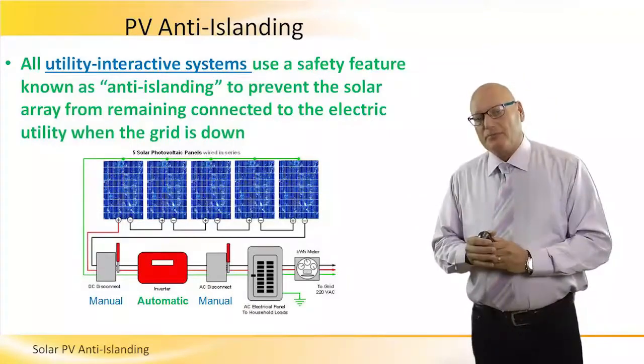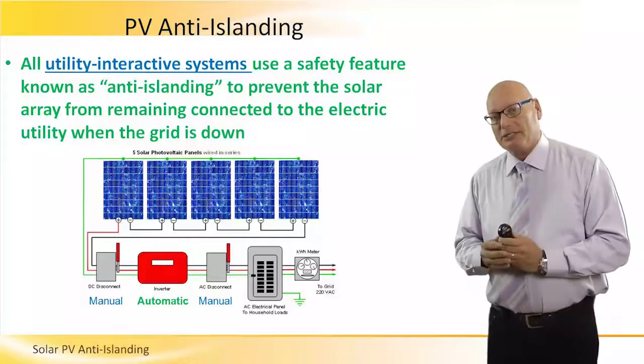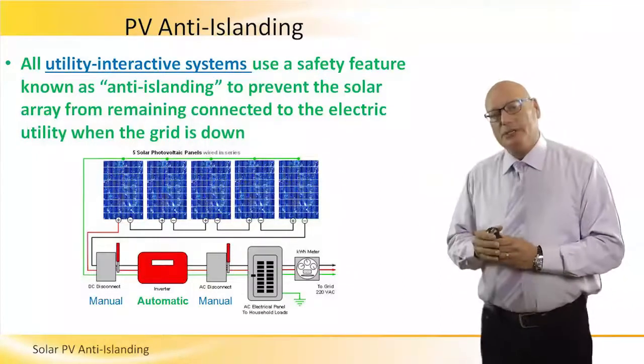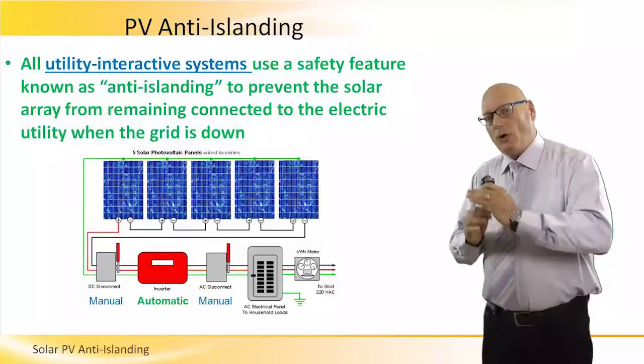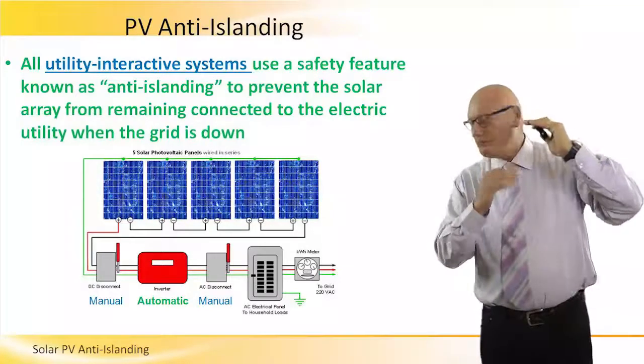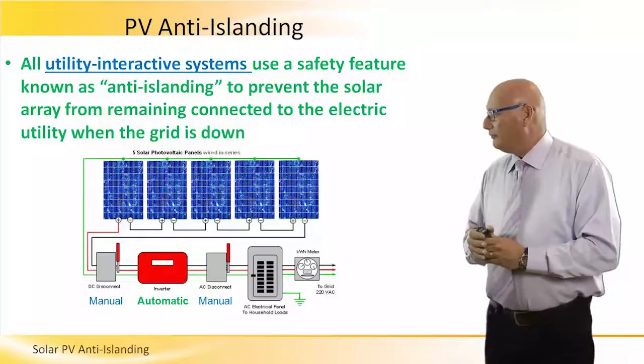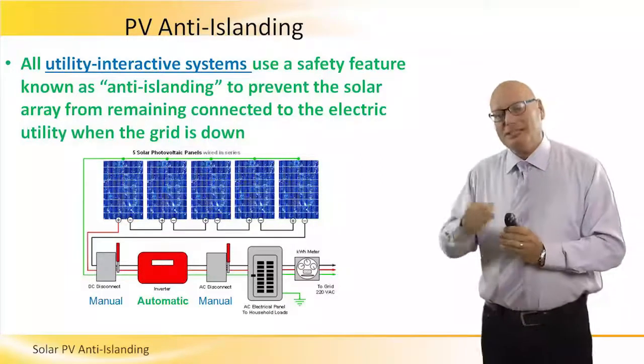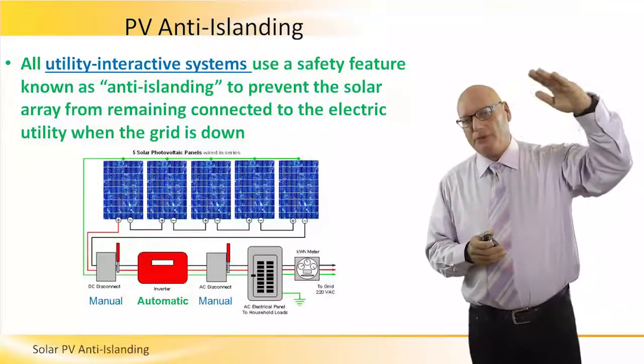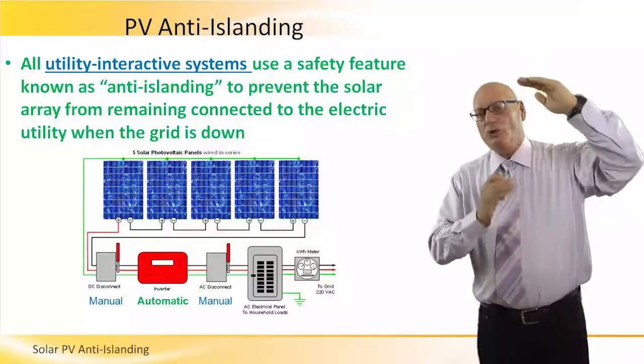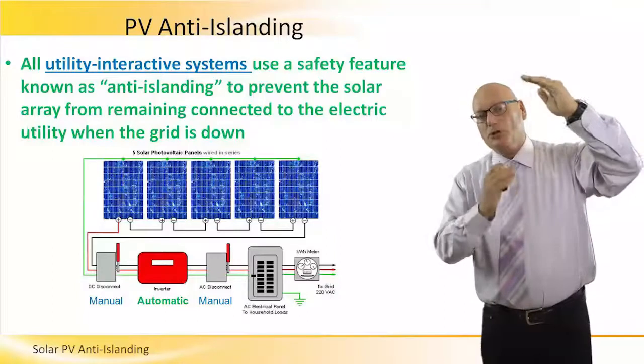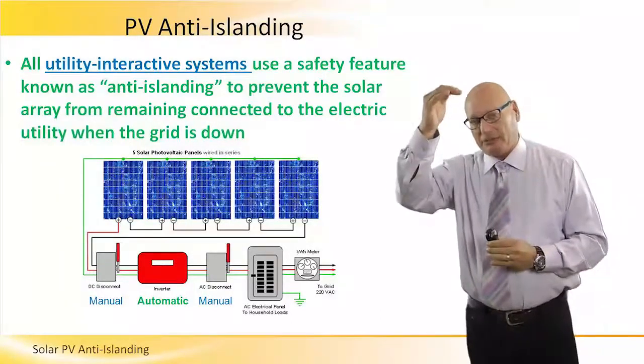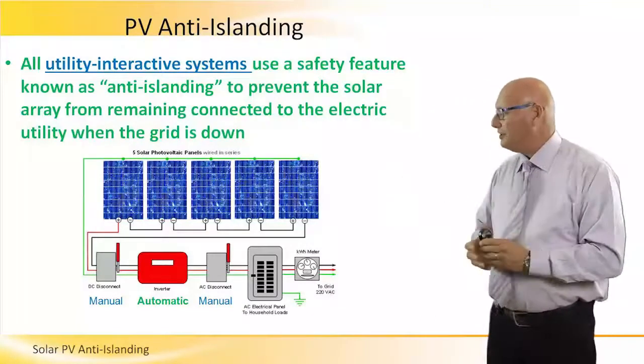On the left is a DC disconnect, because DC voltage comes out of the panels and arrays. The job of the DC disconnect switch is to separate and isolate all the PV array from the entire system. If we need to repair the inverter or anything to the right of it, we first disconnect the DC side in order to separate the PV array, because the PV array continuously and non-stop generates electrical energy as long as the sun is shining.